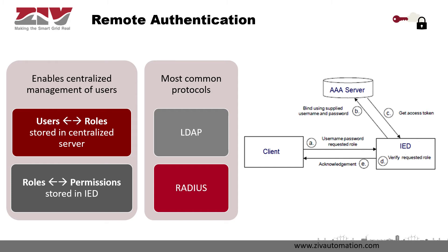Users, passwords, and their corresponding roles are stored in the centralized server — this information is more susceptible to change, so the utility can create, remove, or modify users, change their passwords, and reassign roles. On the other hand, roles and their permissions are defined in the IED and are less susceptible to change; once defined, they are unlikely to change.